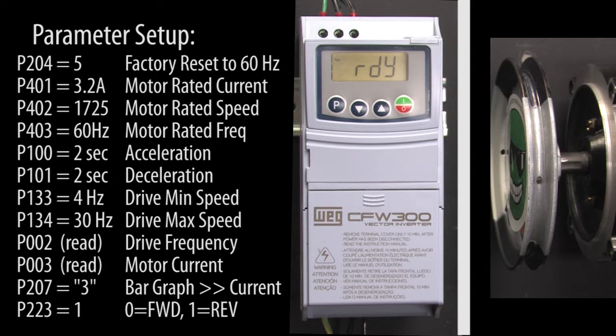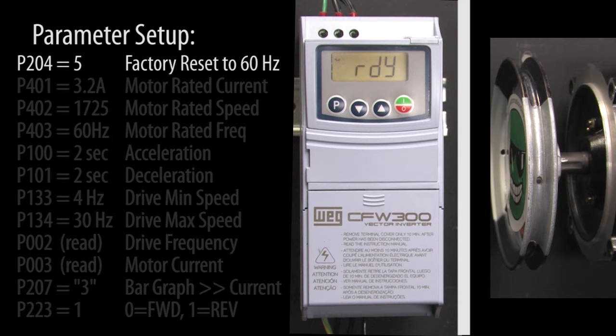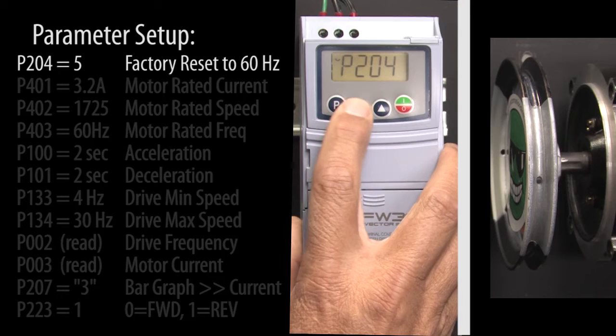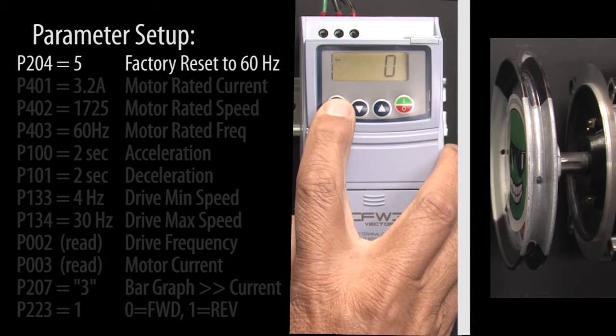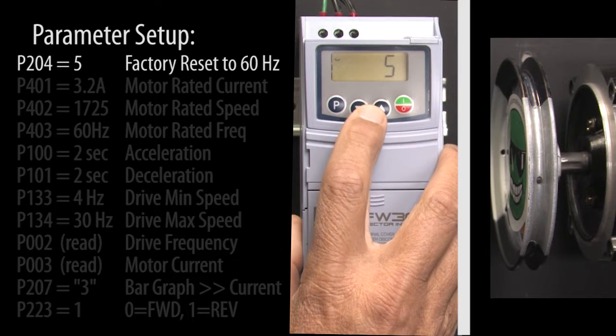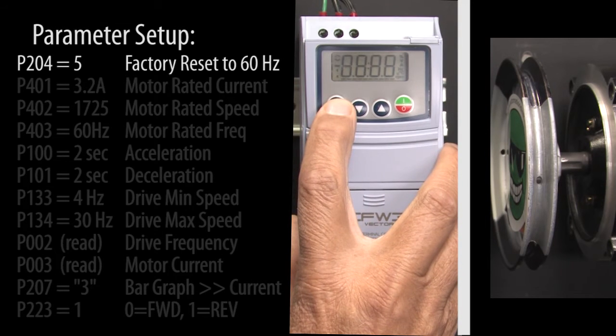Before doing anything, let's reset the drive to factory default so if you're following along we're both starting at the exact same place. Press the P button to get to the parameters and scroll to parameter 204. Hit P again so we can change the parameter to a 5 which resets the drive's parameters to factory default for 60 Hz. Press P to accept that.